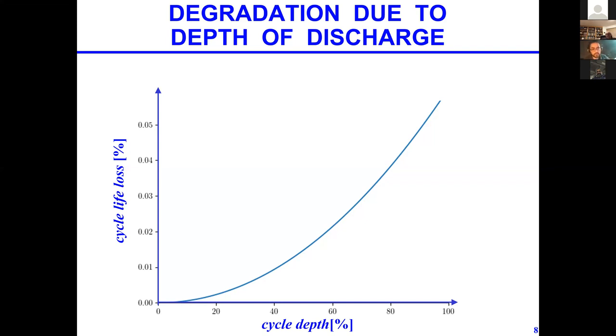So the way the manufacturer says it's usually something like, for example, this battery has 3,000 cycles at 80% depth. Let's think about these numbers. Once you've done 2,000 cycles at 80% depth, you've already spent those 2,000, and you have 1,000 more cycles at this depth. But if you're working with, say, 50 or 40% depth, the life loss is half, so you have double the number of cycles left.